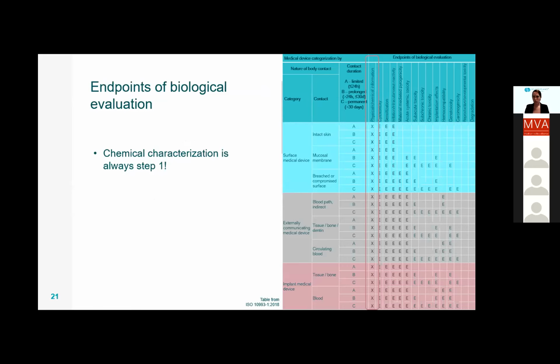I won't go through it in detail, but essentially you make a categorization of your device depending on the nature of body contact and the contact duration. So essentially, the more invasive the device is and the longer the body contact is, the more endpoints you need to consider in your biological evaluation. But one thing that is new with this 2018 version of this table is that physical and chemical information has been included in the table, and it's marked with an X to really stress that this is step one, which you should do before you decide on any of the other tests in the table. Next slide, please.